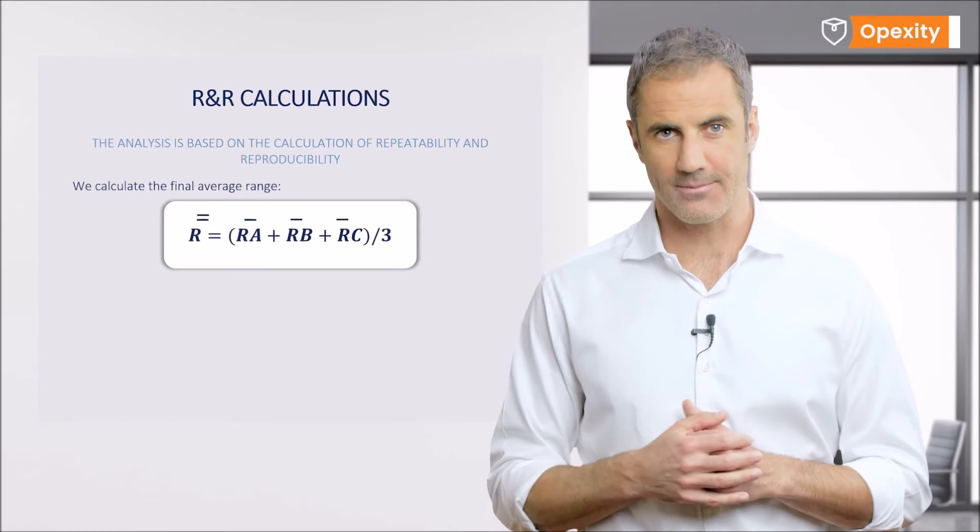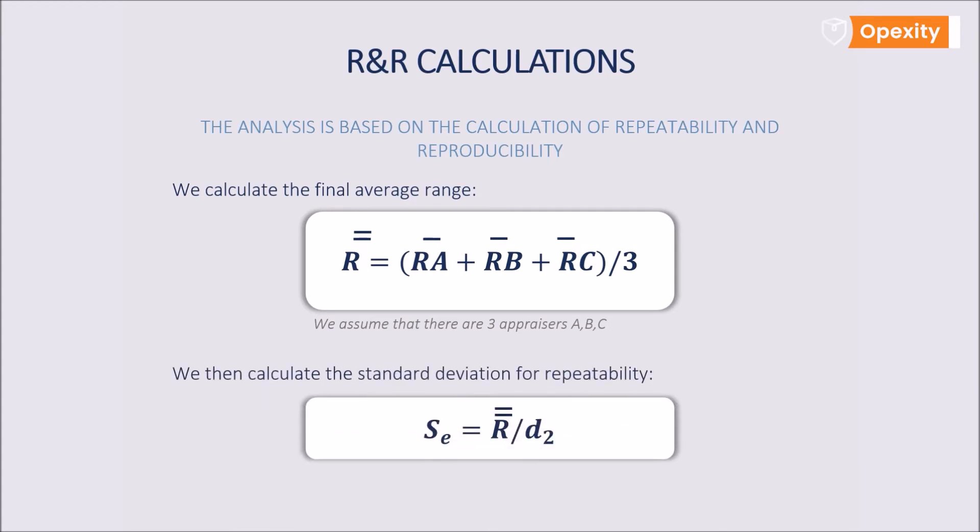Having the average of ranges as generated by each appraiser, we can calculate the final average of the range for the whole study. We add the individual ranges together and divide by their number. Now we will have to look at the statistical tables and calculate the value of the standard deviation SE for repeatability. This can be done by dividing the final average of the range by the parameter D2 that can be taken from the appropriate table. This is a normal distribution parameter that depends on the number of parts measured and the number of tests conducted.